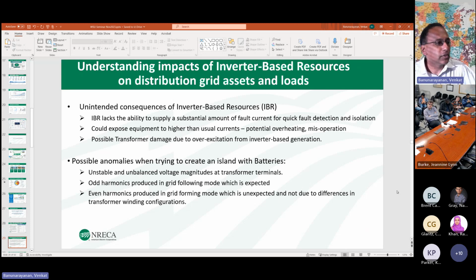What are some of the consequences of inverter-based resources? The biggest one is fault current, right? You all know that. It's high impedance equipment, and therefore it's a low amount of fault current. It's not high enough to trip. It's not as low as a steady state current. It's somewhere in between, which means if it's not tripped, loads are exposed to higher than normal currents and increased heating, and therefore can suffer additional wear and tear without anyone being aware of the reason for it, right?